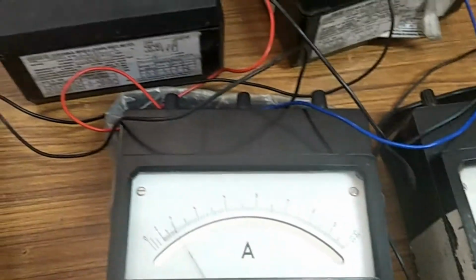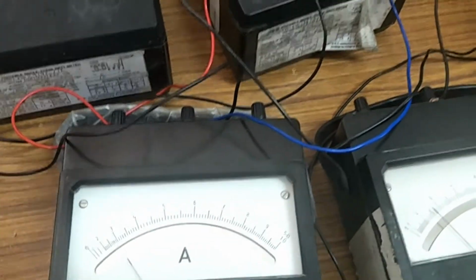Is it clear? And you have to take the readings up to the rated values of the secondary side. The secondary side rated current, as calculated here, is 8.6 amperes, and you have to ensure that on the primary side also the current rating should be 5 amperes. So up to 5 amperes on the primary side and up to 8.6 amperes on the secondary side, vary the loads and note down the readings as shown here for the balanced condition.